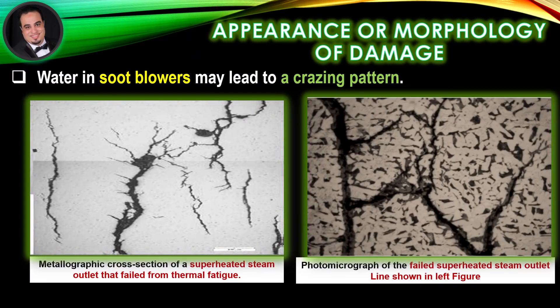Water in soot blowers may lead to a crazing pattern. The predominant cracks will be circumferential and the minor cracks will be axial. As illustrated in figures, a metallographic cross section of a superheated steam outlet line that failed from thermal fatigue, and a photomicrograph of the same failed superheated steam outlet line.